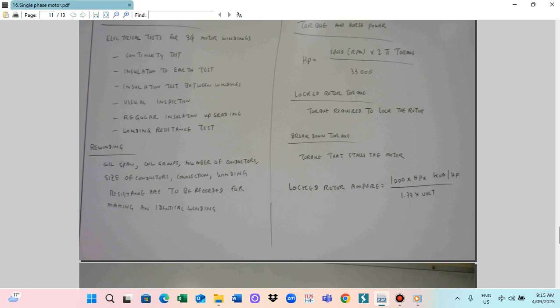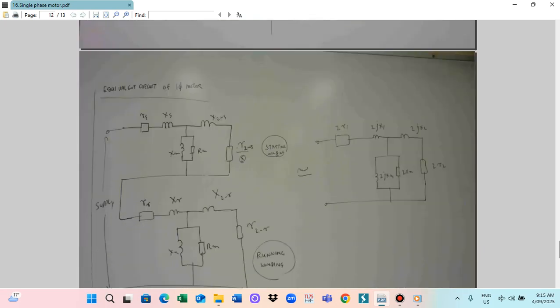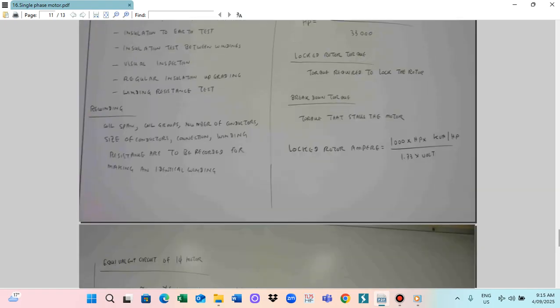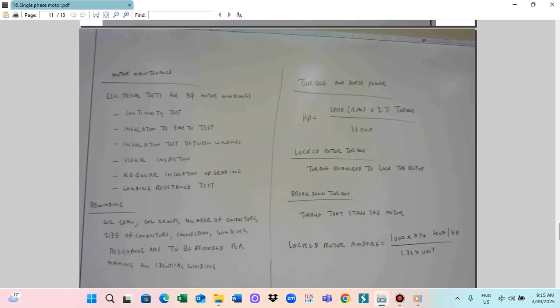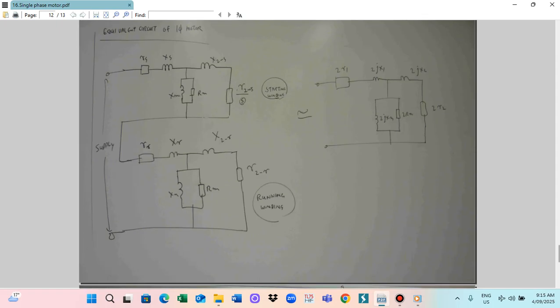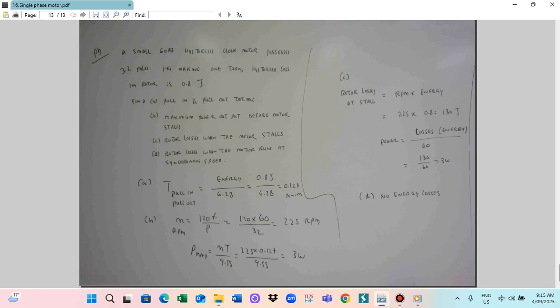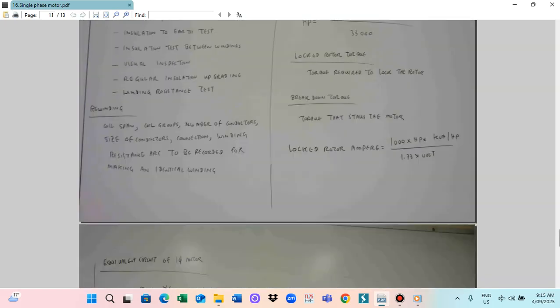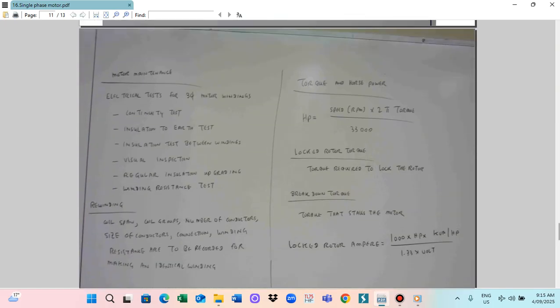Motors have code letters. Motor windings have the code letters A, B, C, D. Depending on the kVA per horsepower, we call it the motor code letter, which you see on the motor. So motors are type A, type B, type C, type D up to type V. In this case, kVA per horsepower will range from 0 to 3.15 up to 22.4. This is for the locked rotor rating.